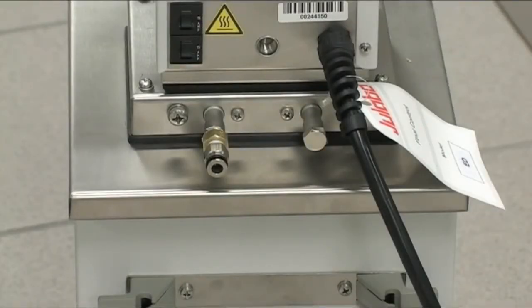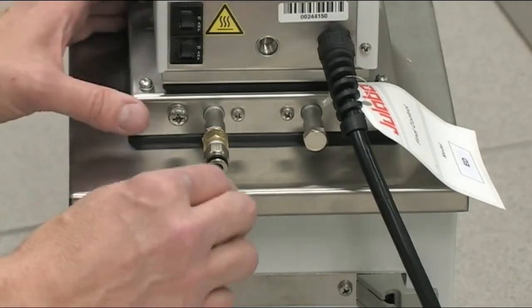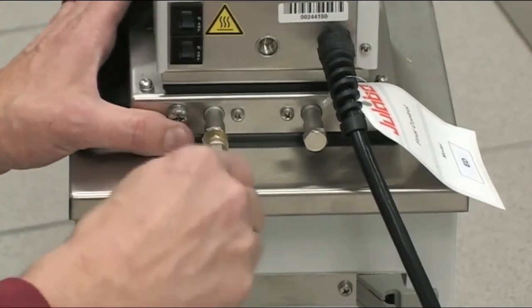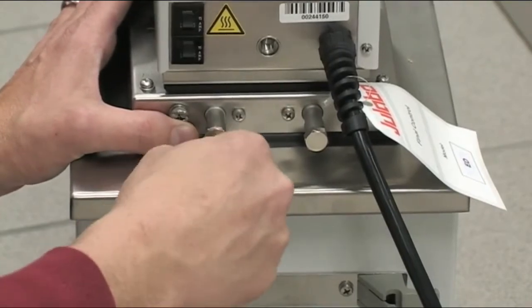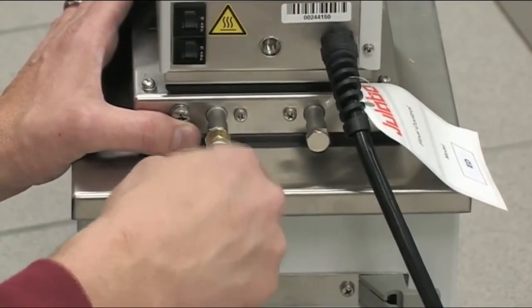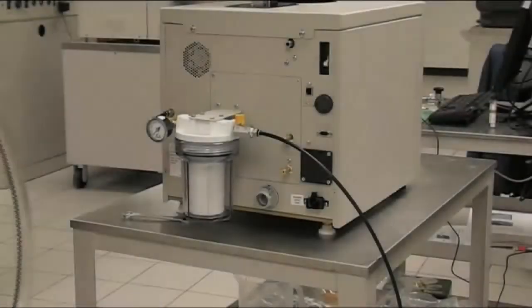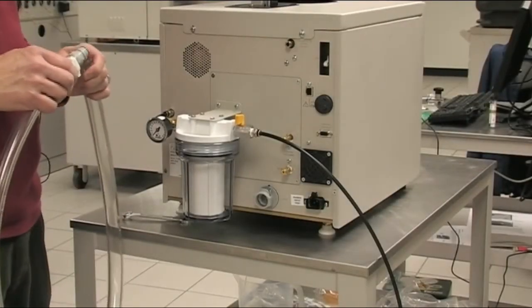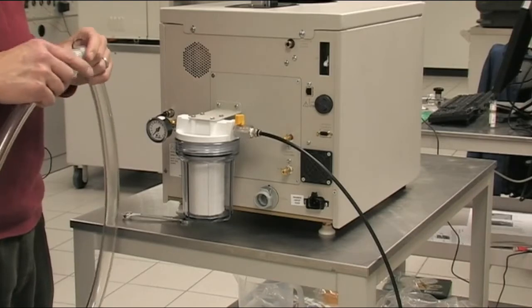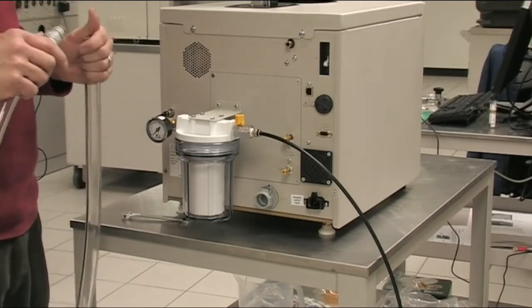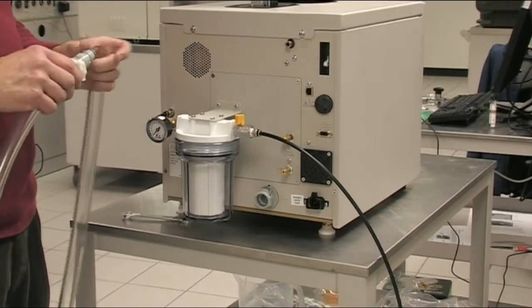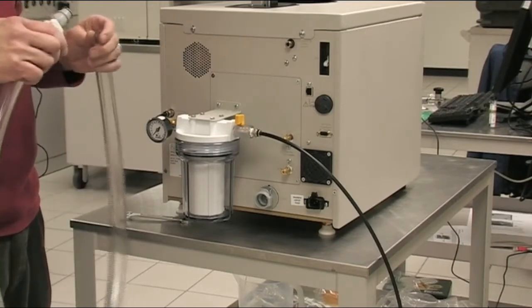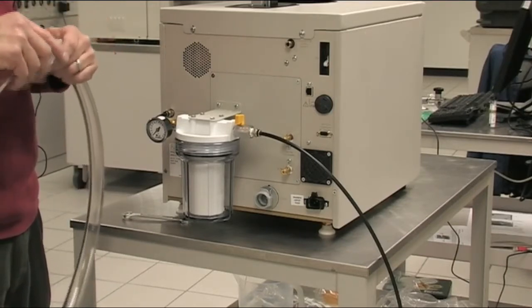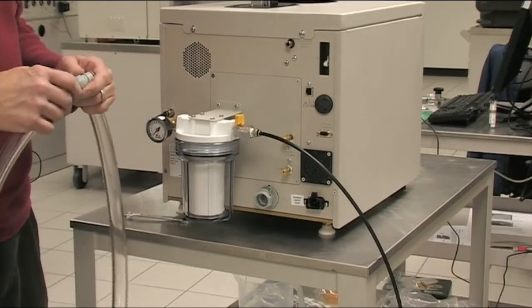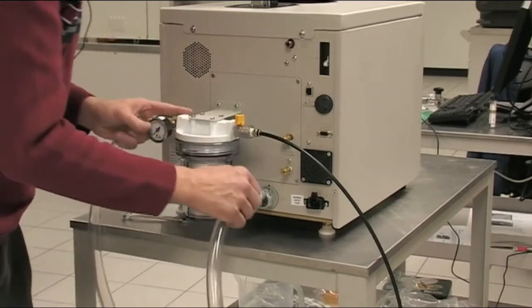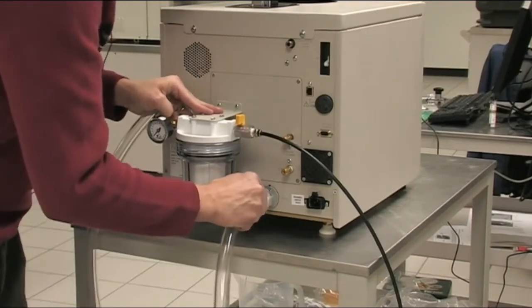Next thing you want to do is take your feed line to the instrument and plug it into the feed line of the pump. Insert it firmly in and pull back to make sure it is firmly attached. Next thing we're going to do is cut the drain line to length. The length has to be as close to a straight line as possible to the chiller. You don't want any kinks in the hose or any loops for the drain return line because you don't want the water to hang up. You want it to go straight to the chiller. What you'll then do is plug the drain line into the back of the instrument.